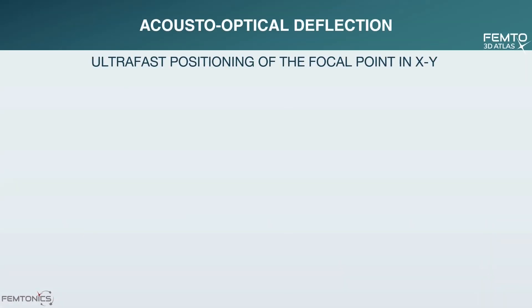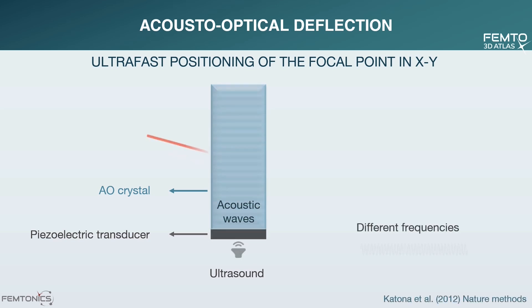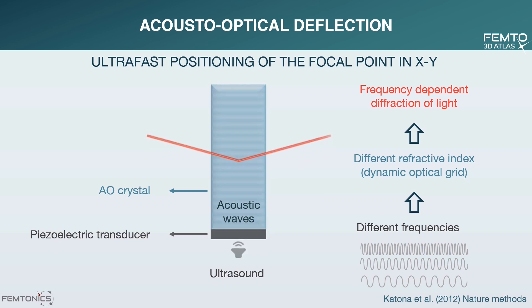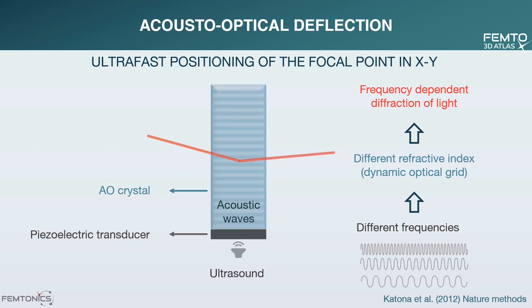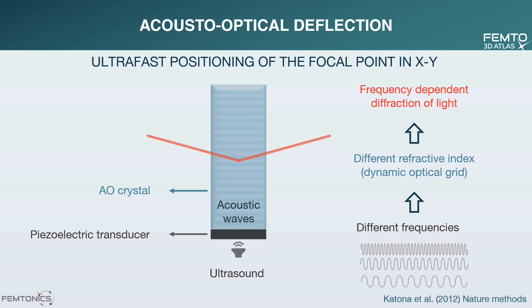So what exactly is the acousto-optical technology? An acousto-optical deflector consists of a tellurium dioxide crystal bonded to a piezoelectric transducer. The transducer emits an ultrasound wave to the crystal when driven by a sine wave. Sound waves in the crystal generate periodic changes in density and therefore the refractive index, creating a dynamical optical grid that deflects light falling through the aperture. Changing the frequency of the sinusoidal voltage changes the constant of the optical grid and thereby the angle of deflection. Note that as long as the acoustic frequency is unchanged, the deflected light beamlets are parallel to each other and are not focused.